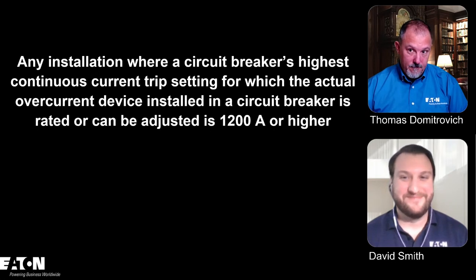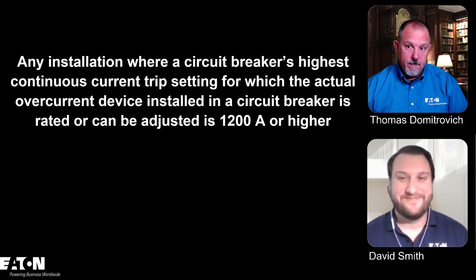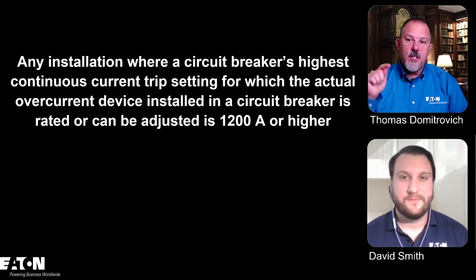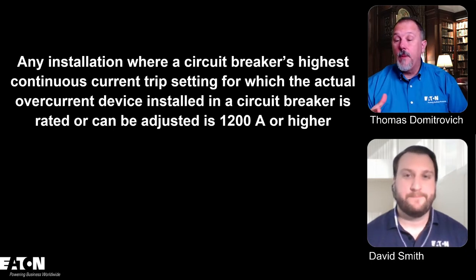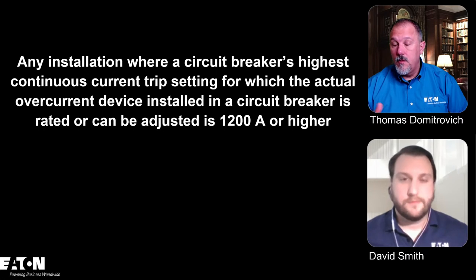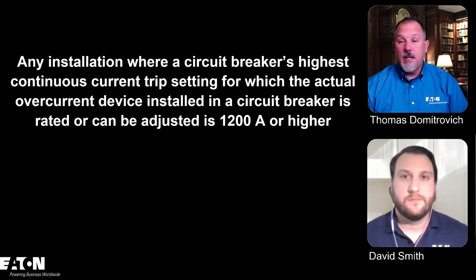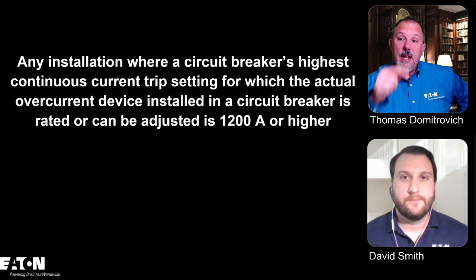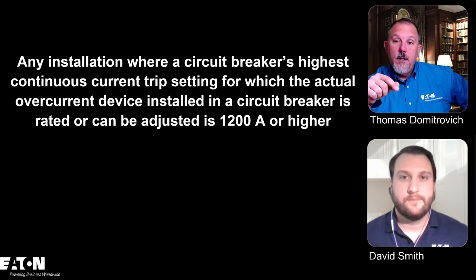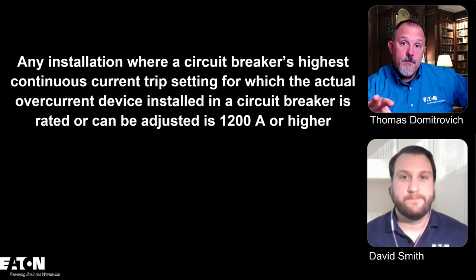So let's first talk about the actual overcurrent device installed in a circuit breaker. What we're talking about there is your trip unit, right? Yep. It could be a rating plug. Sure. So I could have a 1200 amp frame breaker. I could have a rating plug that's 1000 amps, meaning I can't go any higher than 1000 amps. Right. And so the overcurrent device that's installed in that circuit breaker is only 1000 amps. So this wouldn't apply. Right. Correct.